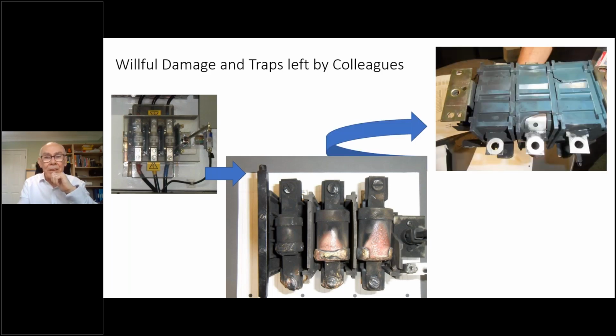If I turn the unit over, you can see the monoblock is cracked. If you look at the center photograph again, you'll see there are physically three different size fuses in there. Someone in the past tried to force in a fuse that wasn't meant for that particular switch fuse, which created the damage. I'd call that willful damage, and also a bear trap left for colleagues, because people were burned as a result of it. These weren't the people who changed the fuses.